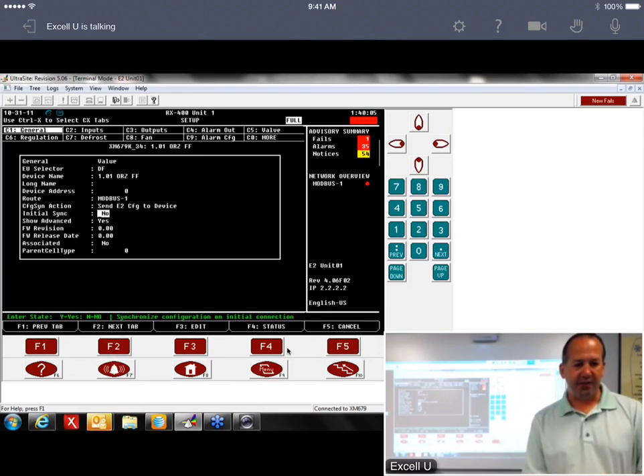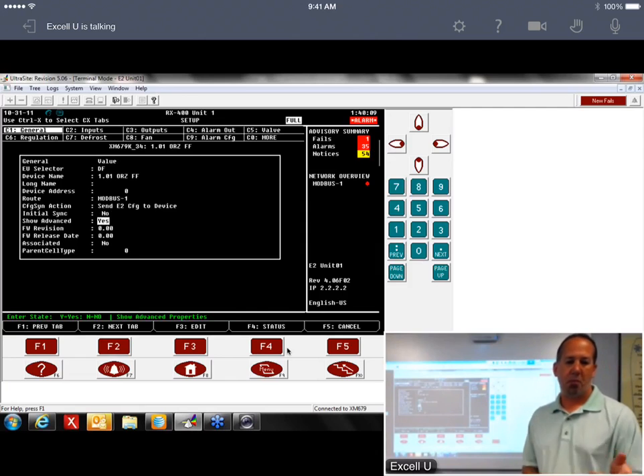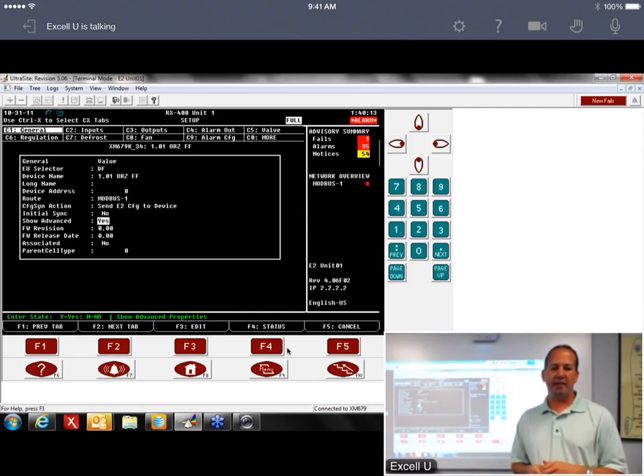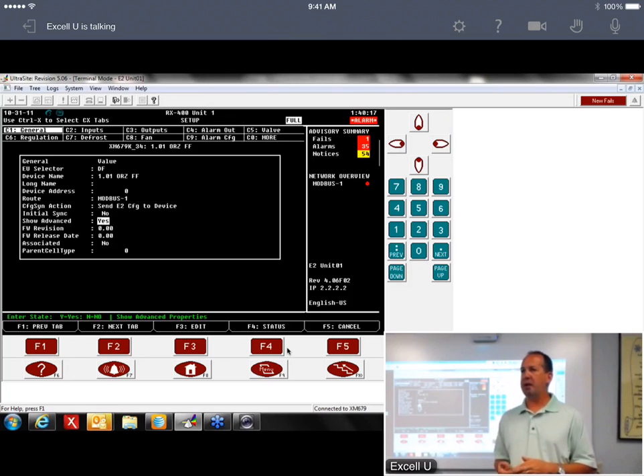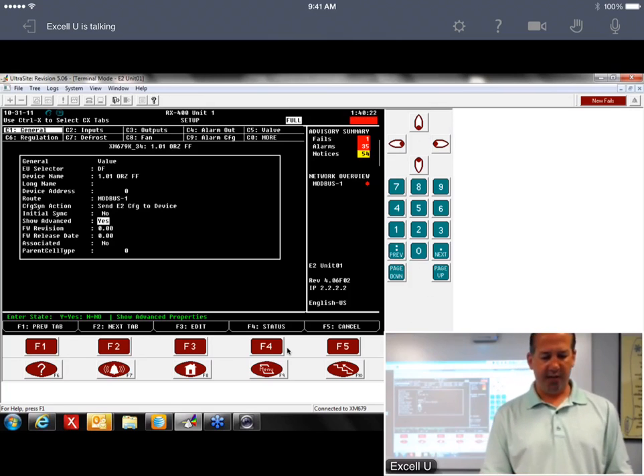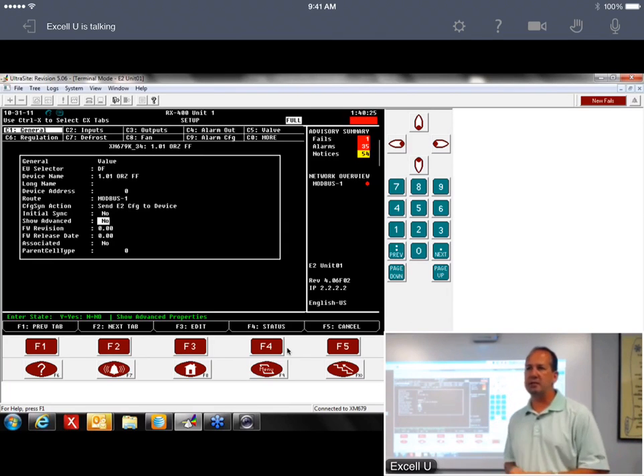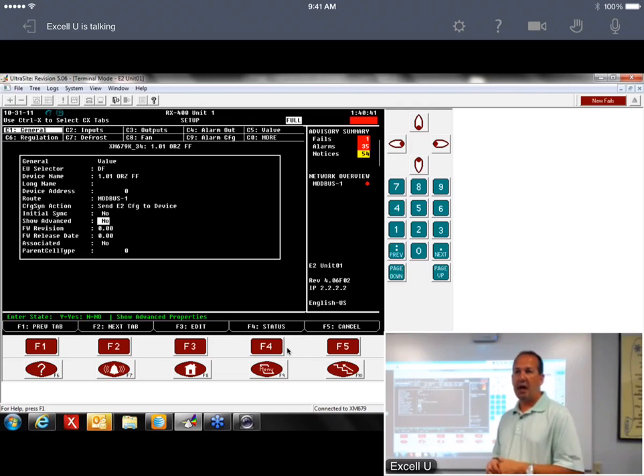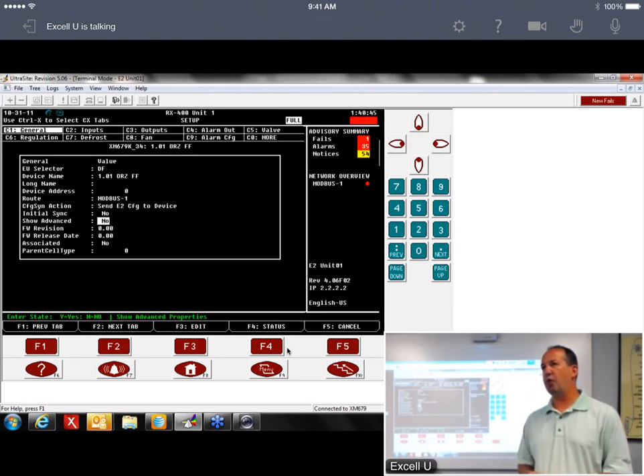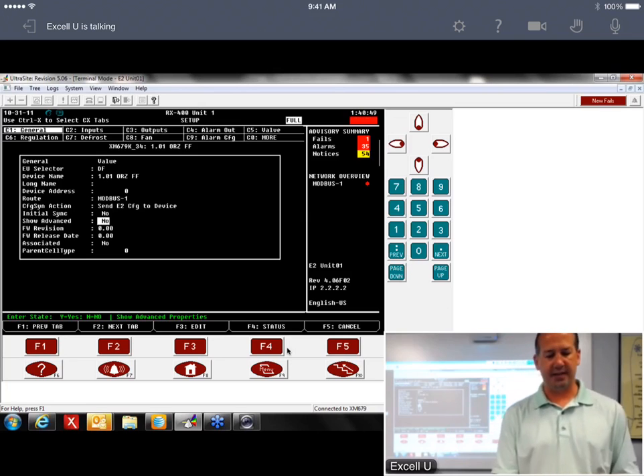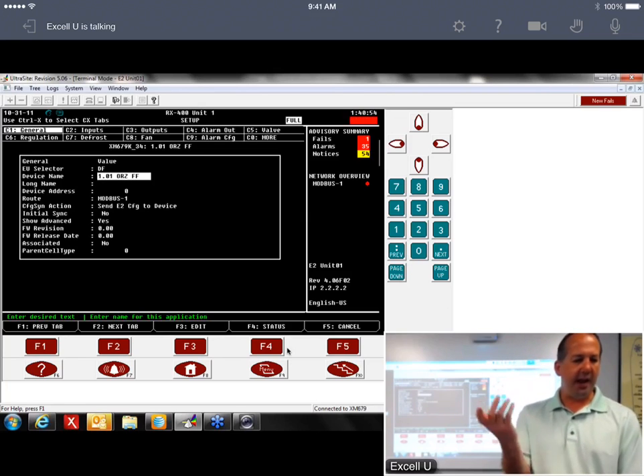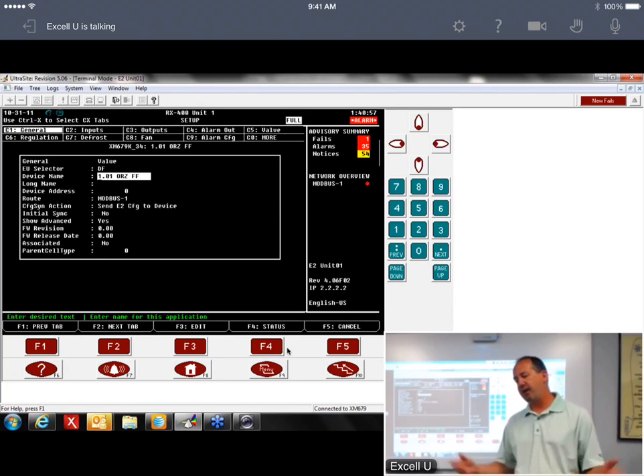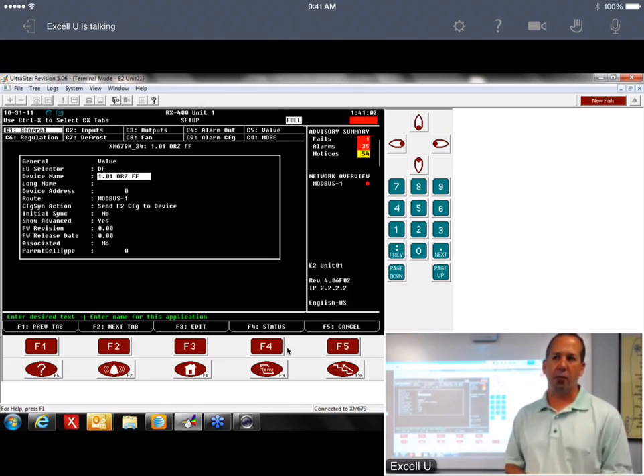Show advanced is another parameter on here. Usually for a service guy, show advanced can be left to no. But if you're programming initially, there's a couple parameters you're going to need to see. So what this does, if it's set to no, it hides a whole bunch of stuff. There's 300 parameters in this device, and most of them, I'd say 280, you don't even need to mess with. So set it to no or yes? Well it depends. If you're doing your programming, I'd have it set to yes. After that, it can be set to no, and it'll hide a bunch of stuff you don't need. But there are some things in the initial program you'll need to see, so I'd say yes, and it's not a big deal. If you set it to yes and leave it there, you're just going to see a whole bunch more parameters, a lot more stuff.